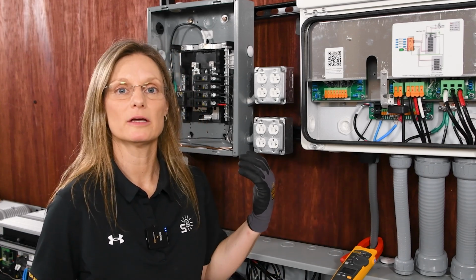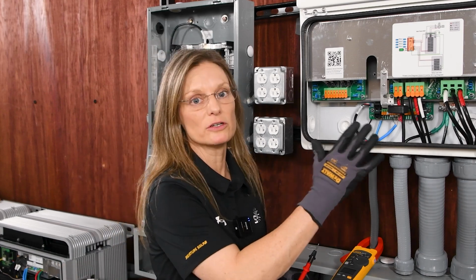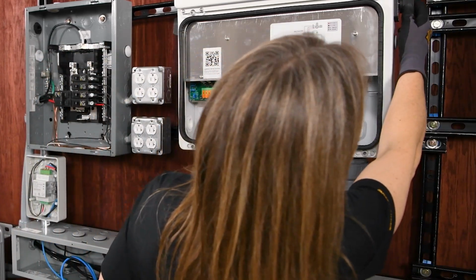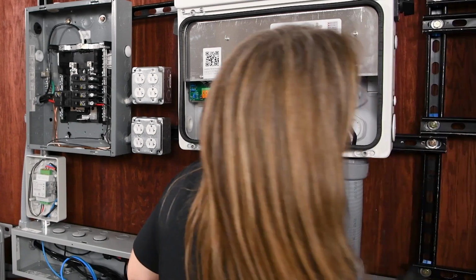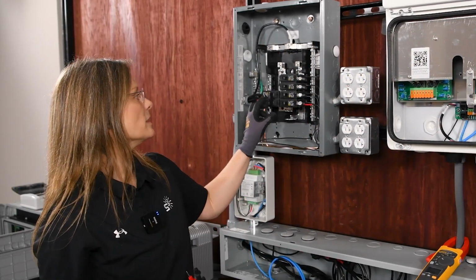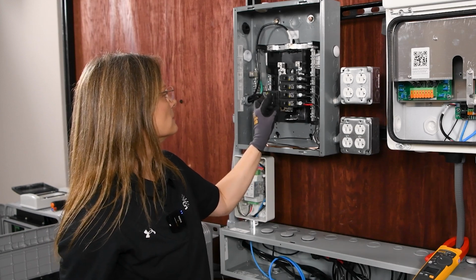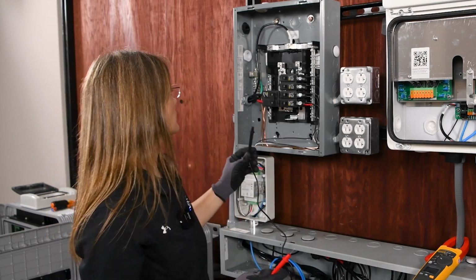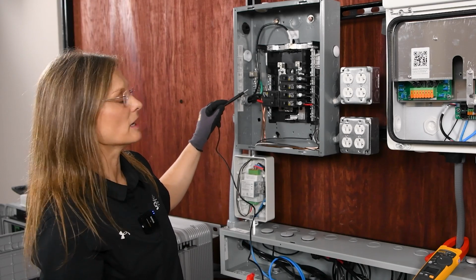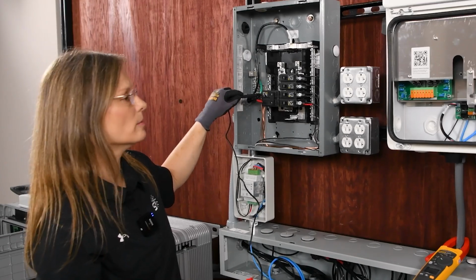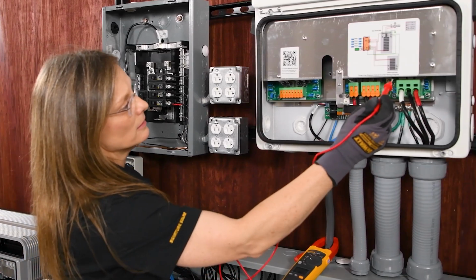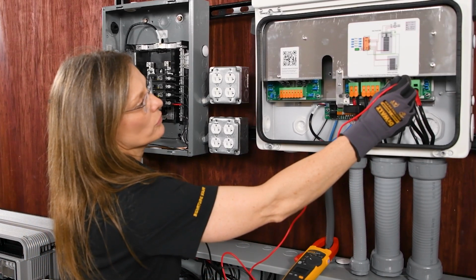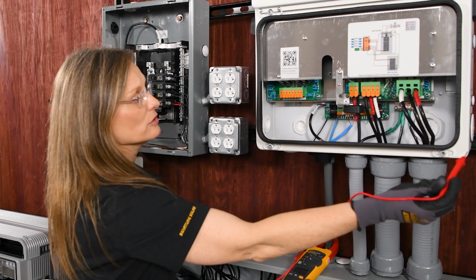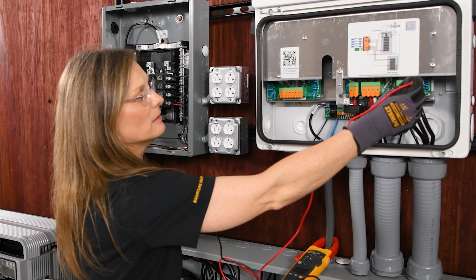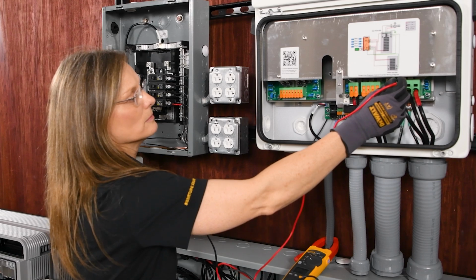So now we'll check for continuity on our phases from our grid to our backup panel. What we'll first need to do is flip our inverter to the bypass, which is on our knob over here on the right. We'll flip it to where it says bypass. We'll also turn on our main breaker on our backup panel. So we'll start with our L1. These should be our black wires. We'll put our black probe on our black wire and on our grid. We have continuity there. To make sure that we don't have continuity, we can check it with the red and with the neutral.